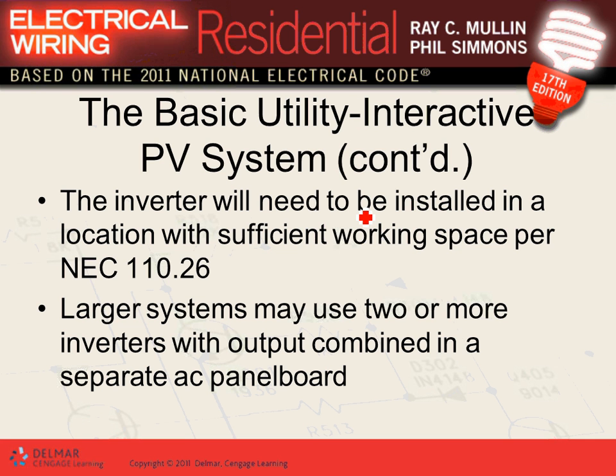Okay, inverters. When you put your inverter, guys, we'll talk about the inverter in a second. As you think, you have to put it in a place where you have ample working space. You have to have a minimum of 3 foot working space on the front of the inverter, like any other panels' working space.